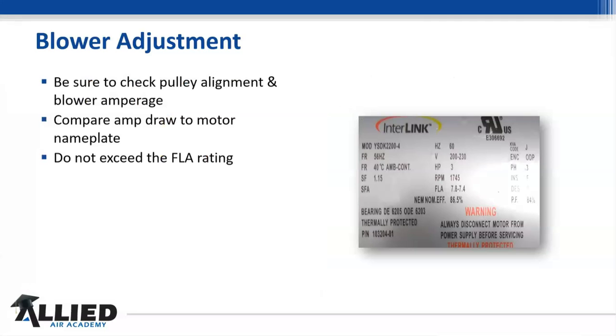One of the most overlooked things is the little tag that's on the motor itself. It gives you a lot of good information, and I want to focus in on our service factor, SF, right here, of 1.15. And you'll see the full load amps on this tag, 7.8 to 7.4. Just for math purposes, I'm just going to say 7.5.